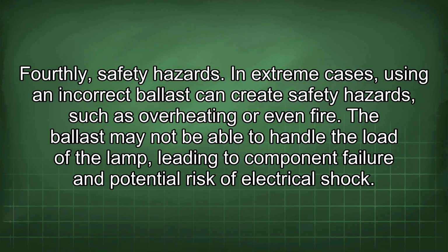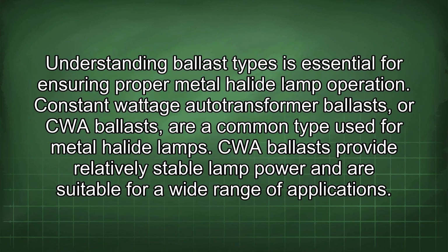The ballast may not be able to handle the load of the lamp, leading to component failure and potential risk of electrical shock. Understanding ballast types is essential for ensuring proper metal halide lamp operation. Constant wattage autotransformer ballasts, or CWA ballasts, are a common type used for metal halide lamps. CWA ballasts provide relatively stable lamp power and are suitable for a wide range of applications.